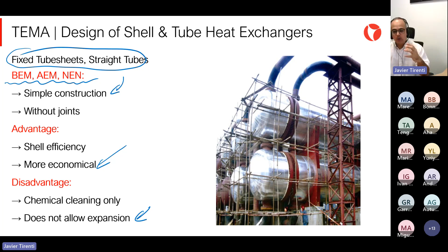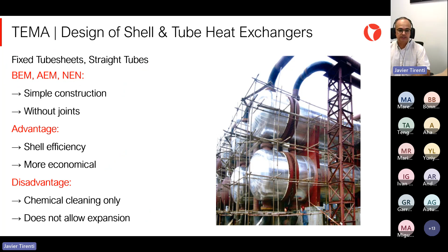Then what can we say about these types of shell and tube heat exchangers? Well, the construction is simple compared to the other groups. And that simple construction comes with advantages and disadvantages, of course. They are the more economical ones compared to the other groups. However, they do not allow differential thermal expansion between the tube bundle and the shell. Since the tube sheets are fixed, there is one group of components there, so the tube bundle cannot expand in a different way than the shell. That is a huge disadvantage for this type of equipment, especially at high temperatures.